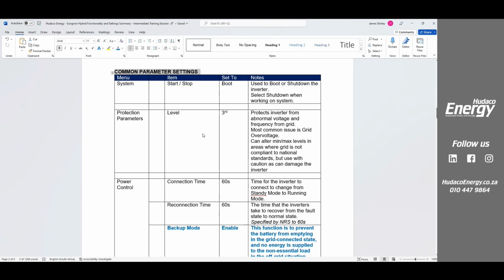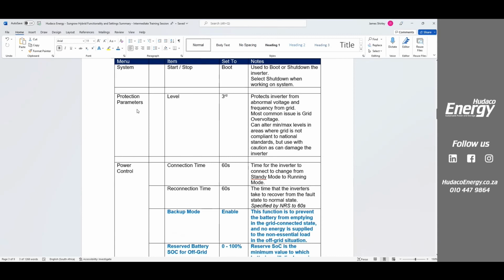We'll cover this a little bit more. This is really talking about low voltage, high voltage, frequency. We set all these parameters in the advanced settings, but the client can choose what level, 1, 2, 3, 4, or 5. Basically, it allows things like high voltage ride through, low voltage ride through, a whole bunch of other stuff. And third is normal.